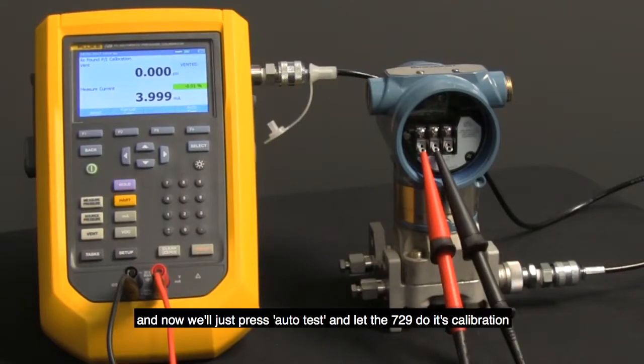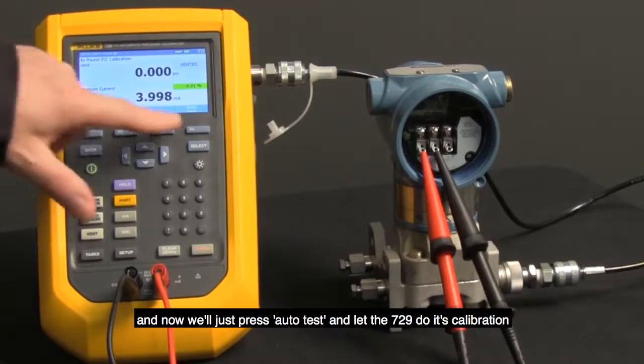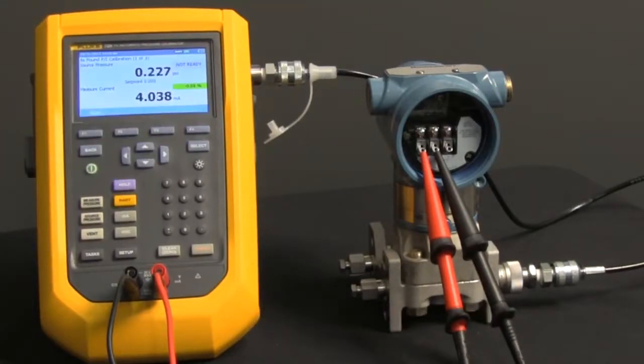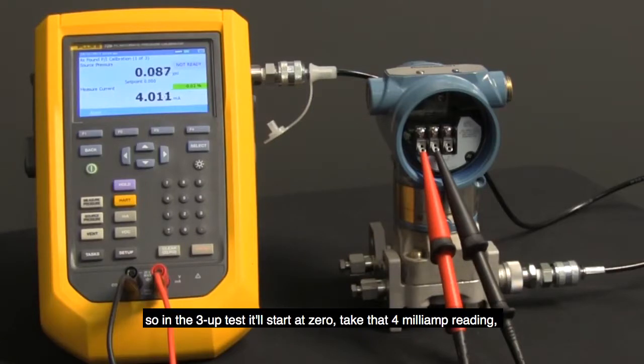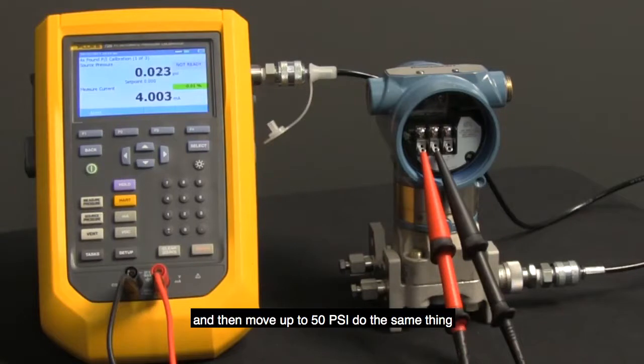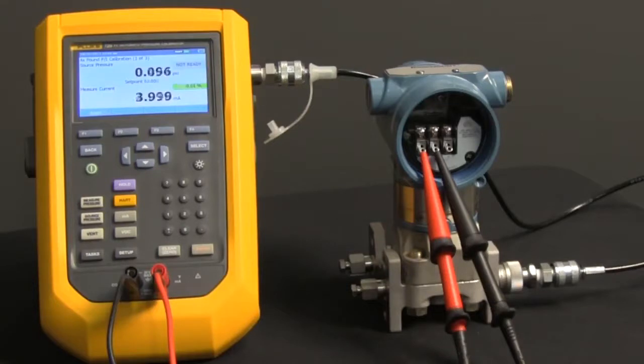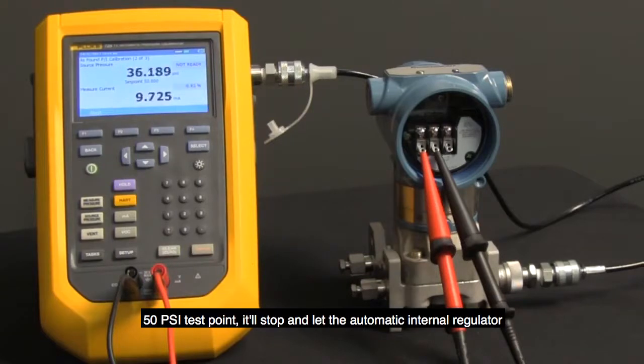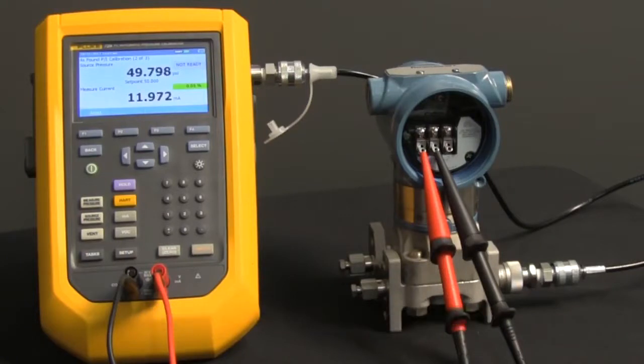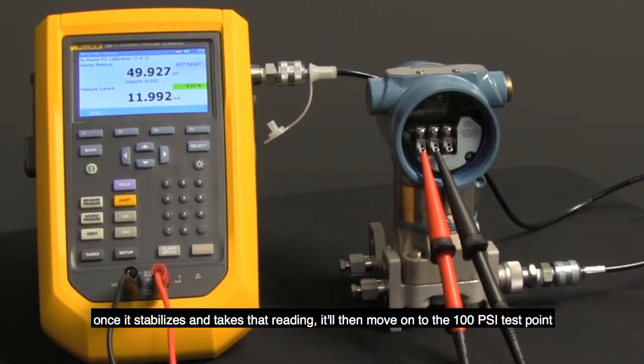And now we'll just press auto test and let the 729 do its calibration. So in the 3-up test, it'll start at 0, take that 4 milliamp reading, and then move up to 50 psi, do the same thing. Notice when it gets up close to the 50 psi test point, it'll stop and let the automatic internal regulator fine-tune automatically and hold steady at that 50 psi test point. Once it stabilizes and takes that reading, it'll then move on to the 100 psi test point.